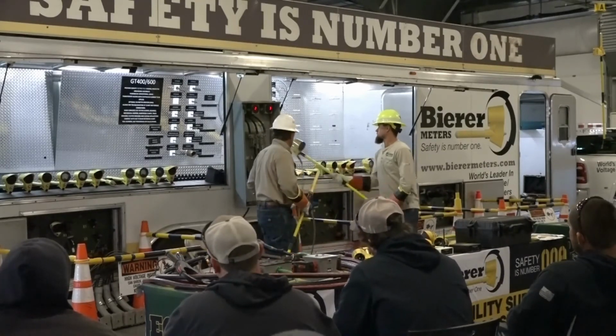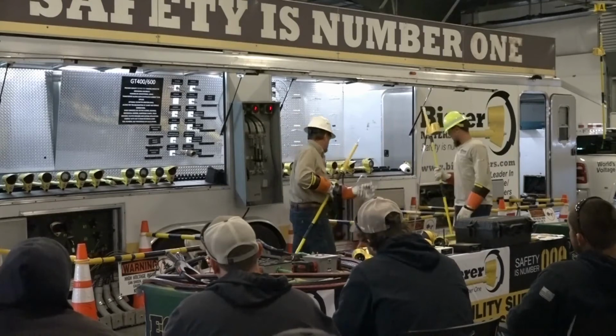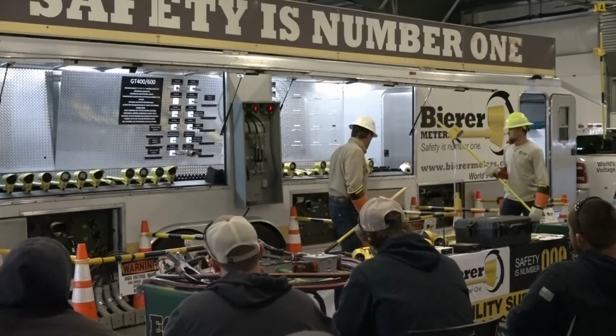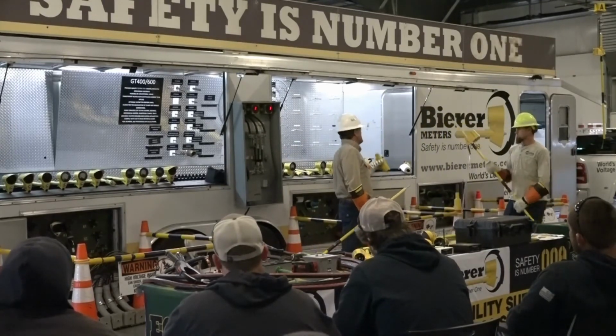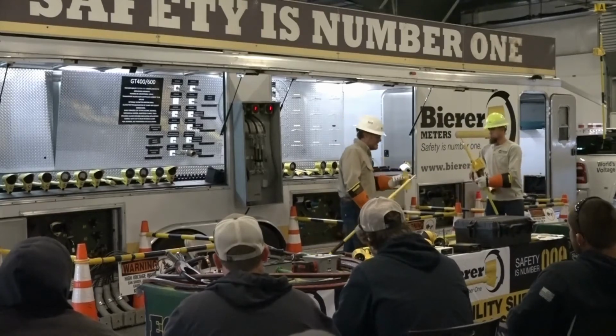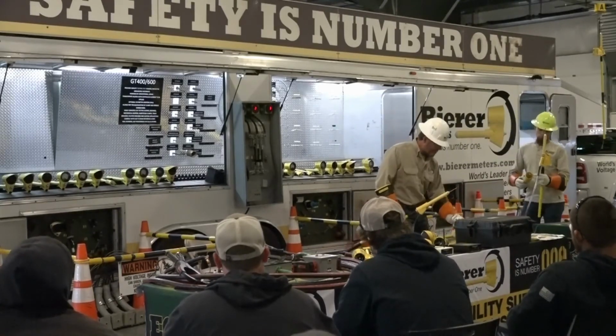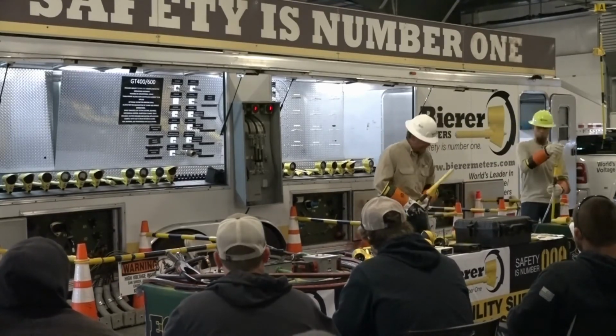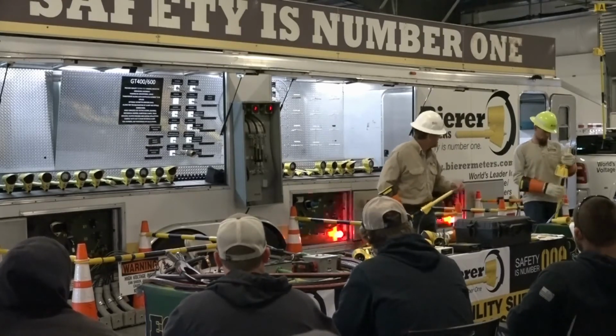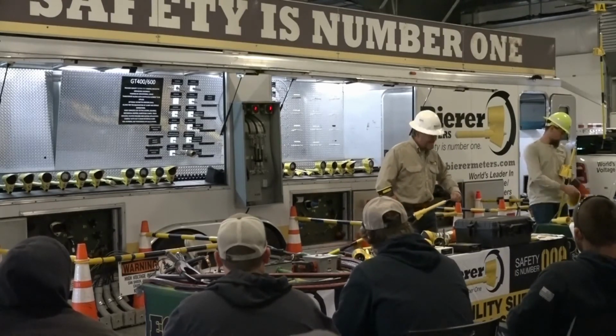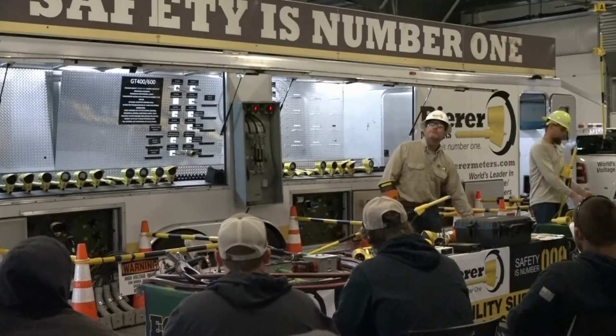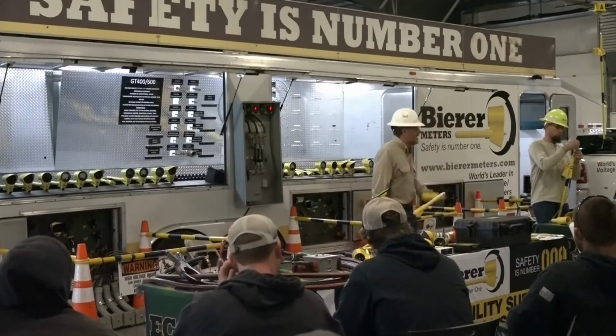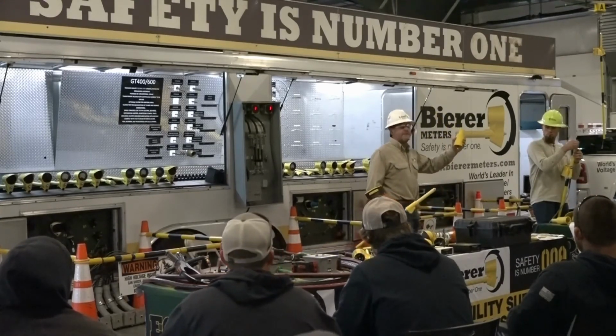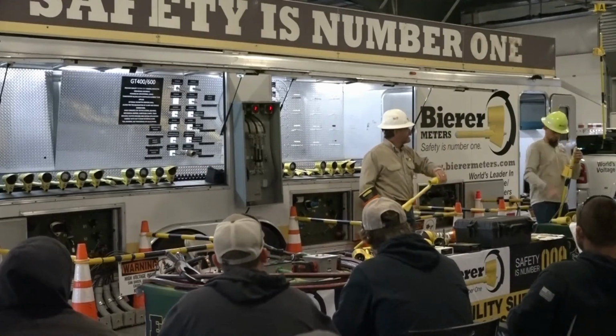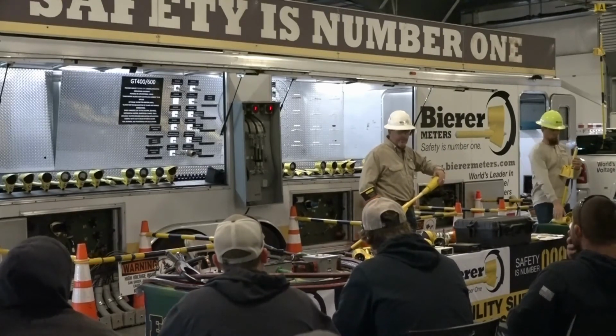Now we're going to phase these hot bushings, Dylan, on what's called our overhead line. Grab your bushing adapter. Let's go to the table and take off your straight probe and switch it out with the bushing adapter. When you guys make an equipment change, like swapping the accessory off the end of our device, you're making an equipment change.